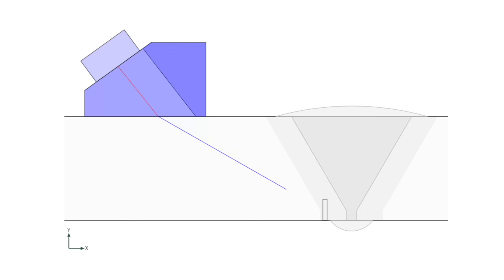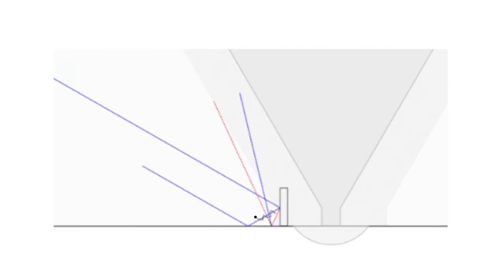Eclipse Beam Tool is totally awesome at illustrating this. Here is a 60-degree beam hitting the notch — it will draw the reflection and the mode conversions. We already know that the reflected shear wave is going to be really weak because we're losing 90% of it due to mode conversion, so I'm going to cross that out. Most of the sound is converted to a long wave, reflecting off the face of the notch and then again off of the back wall.